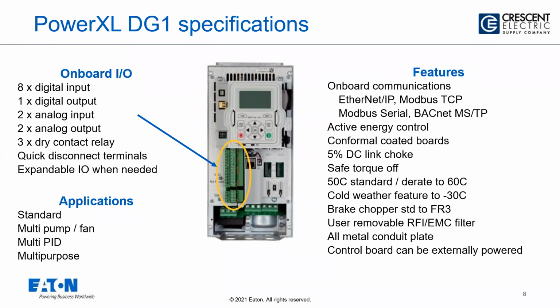So what's really nice about this drive is it's really loaded up from a communication standpoint. You have onboard Ethernet, which is going to be your EtherNet/IP for your control objects, as well as your Modbus TCP. We also have Modbus serial and BACnet MSTP. From an EtherNet/IP standpoint, we also do have on our website for you to use what's called add-on instructions, which will allow you to add that device into your ControlLogix platform. Once again, this has active energy control for the pump and fan energy savings.